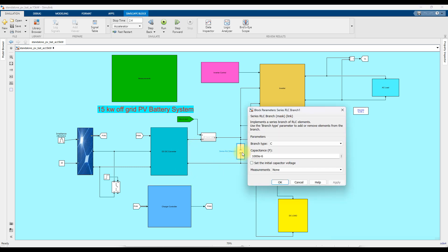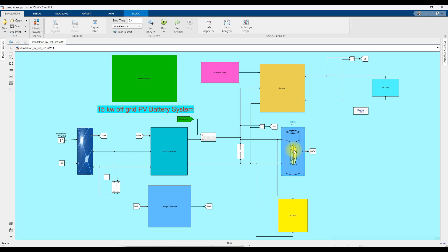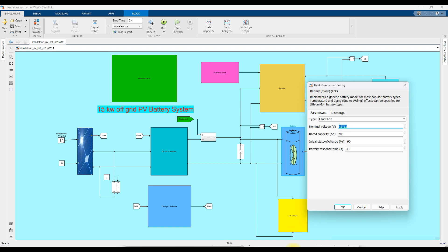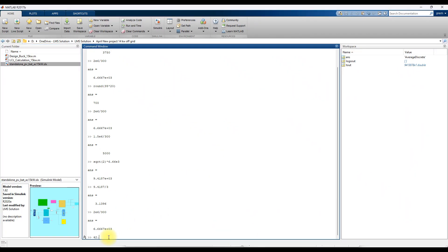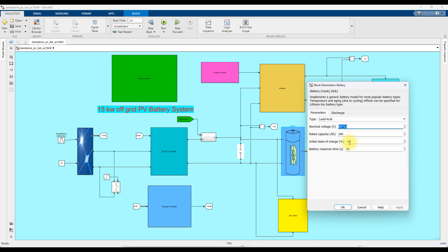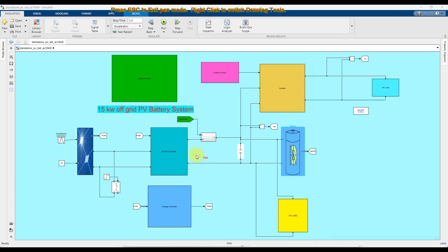Here we have a DC-link capacitor and the battery. The battery rating is 42 batteries in series multiplied by 12 volts, which equals 504 volts total. The rated capacity of each battery is 200 Ah. So by using the buck converter, we are converting the voltage from 750 volts to 504 volts, and also using the buck converter to extract the maximum power from the PV array.